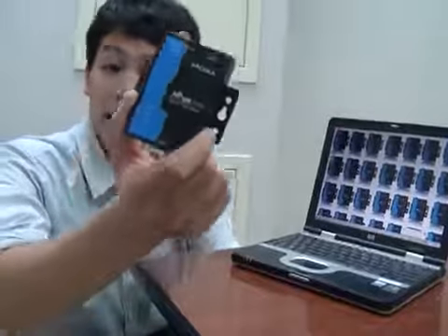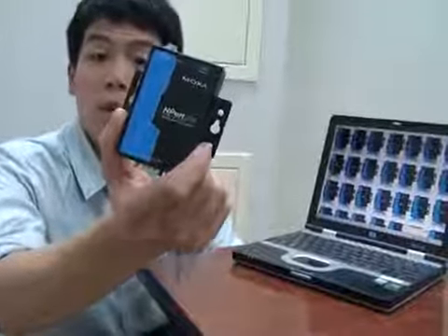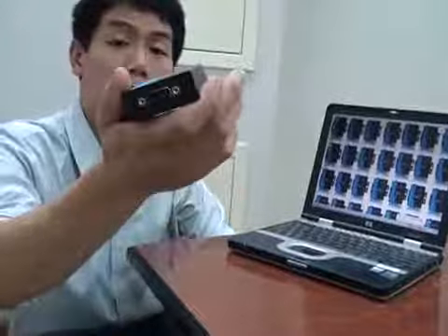Today I want to show you the setup wizard that's built into every NPort A-series device server. We designed this wizard to simplify the installation for the most common field applications. So we're working with the basic one-port model. That's this model, the NPort 5110A. It has one RS-232 serial port.